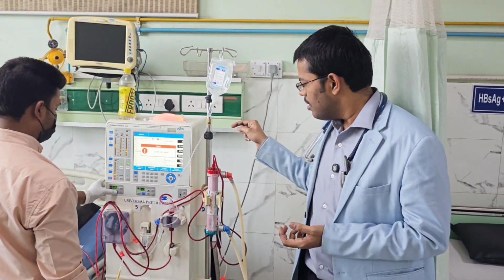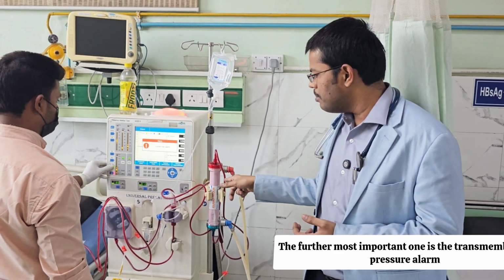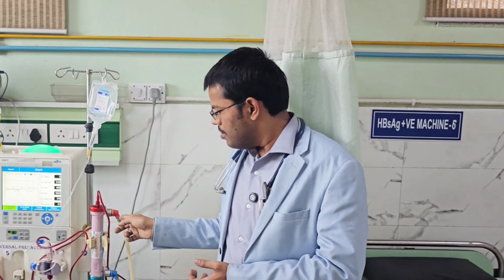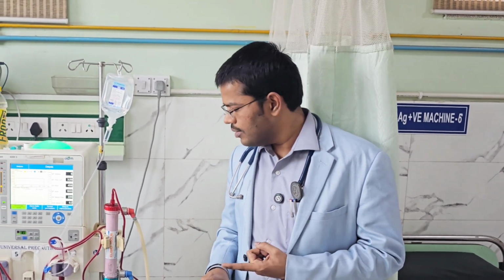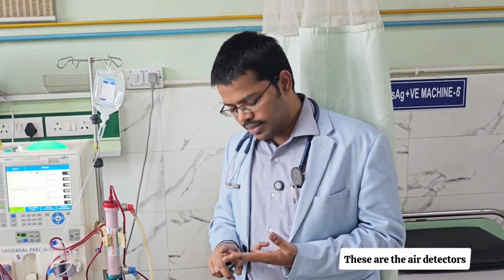Pressure alarm, blood pump alarm, heparin pump alarm: three we have discussed. The next most important one is the transmembrane pressure alarm. We will continue that in the video on dialysis interruption. The pressure difference between the blood compartment and the dialysate compartment is called the transmembrane pressure. If the transmembrane pressure goes above or below a particular limit, the alarm will start ringing. This is called the transmembrane pressure alarm. So overall, these are the alarms related to the blood circuit: blood pump, heparin pump, the air detector alarm, the transmembrane pressure alarm, and pressure. Five related to the blood circuit.